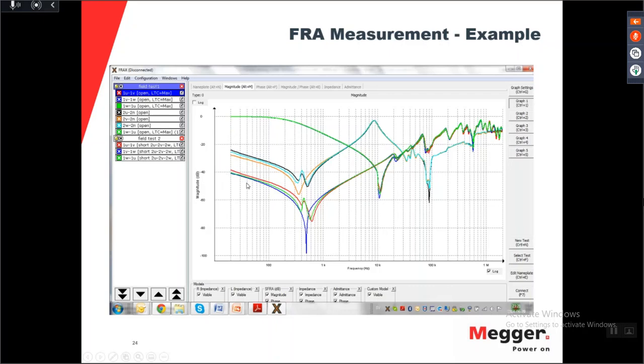For the open tests here, you can see that you have 2 phases that are very similar. You see the blue and the green line here, they are almost lying on top of each other. And the mid phase, the red one, is different from the two other ones. That is a very, very good behavior, and it's typical excitation current behavior, which is the exact same thing that we're looking for in the excitation current test. So here you see two phases behave the same, which is the outer phases of the transformer, and the mid phase, for those of you who attended part 1, you know this, is deviating. When you do the short circuit test, you remove the effect of the inductance. Therefore, phases should be on top of each other.